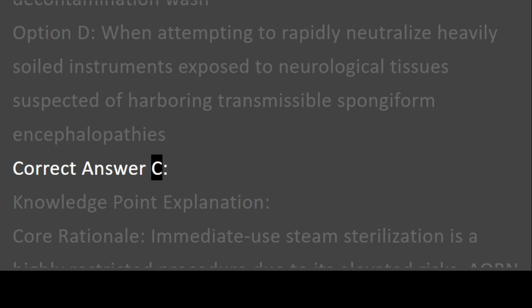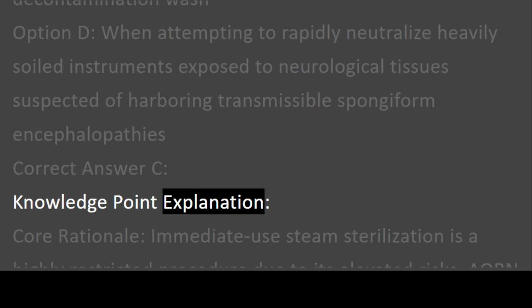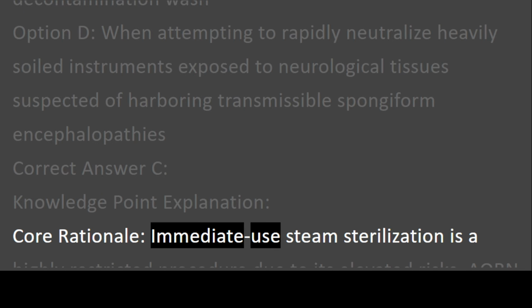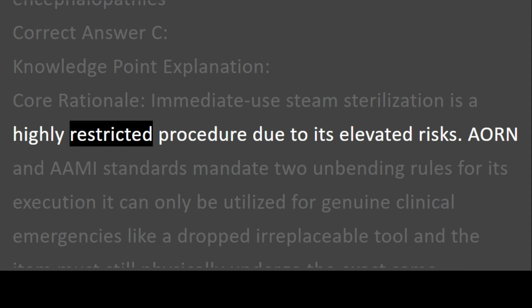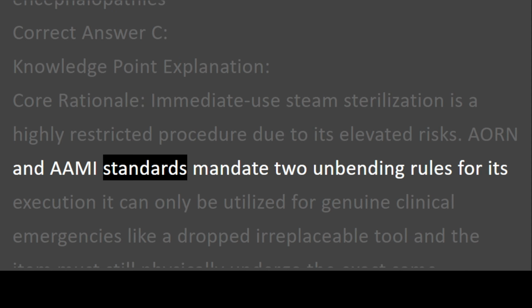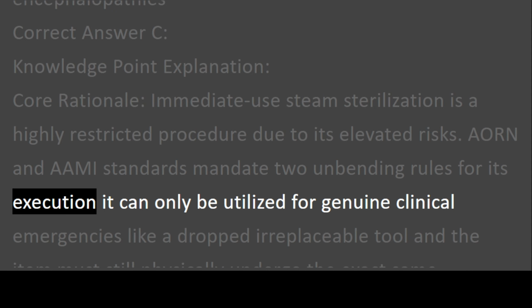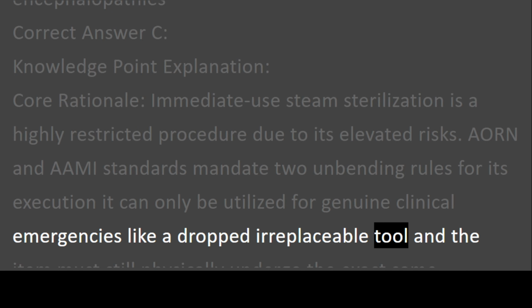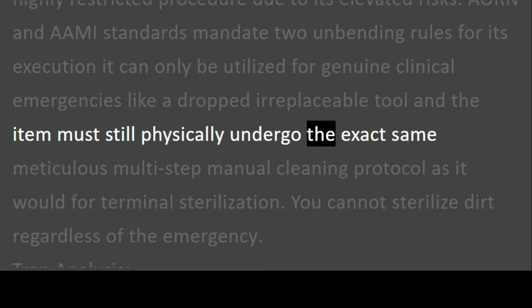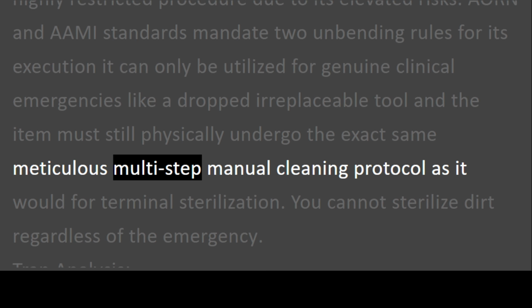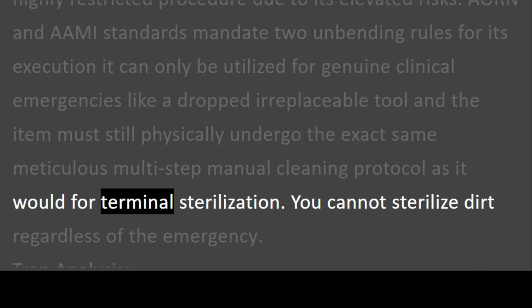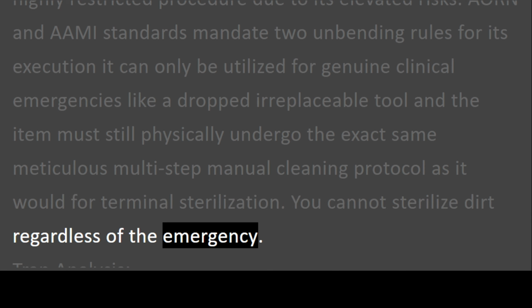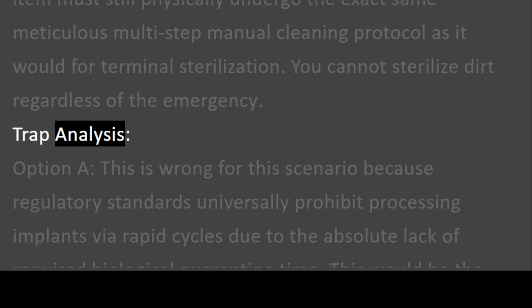Correct answer C. Knowledge point explanation. Core rationale. Immediate use steam sterilization is a highly restricted procedure due to its elevated risks. AORN and AAMI standards mandate two unbending rules for its execution. It can only be utilized for genuine clinical emergencies like a dropped irreplaceable tool, and the item must still physically undergo the exact same meticulous, multi-step manual cleaning protocol as it would for terminal sterilization. You cannot sterilize dirt regardless of the emergency. Trap analysis.